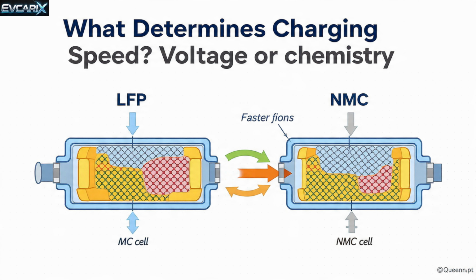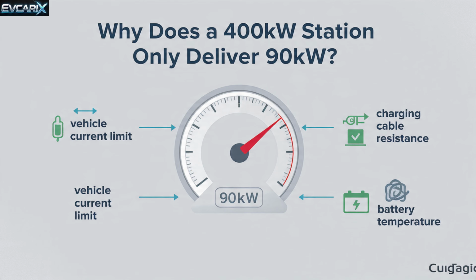To prevent this risk, the BMS proactively reduces the current. In addition, when the state of charge becomes high and the cell voltage approaches its limit, the system switches from constant current mode to constant voltage mode, which automatically reduces power. This is not a flaw. It is a safety feature designed to protect battery lifespan.